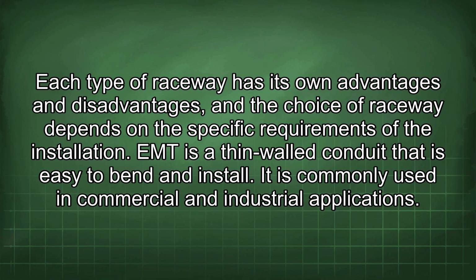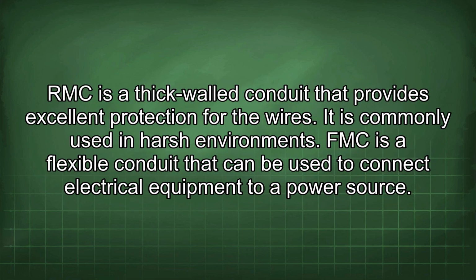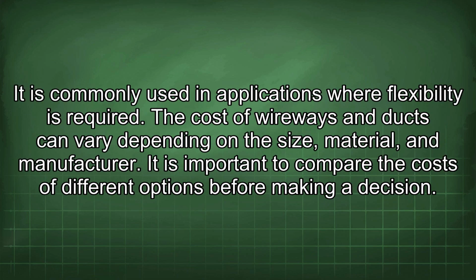EMT is a thin walled conduit that is easy to bend and install. It is commonly used in commercial and industrial applications. RMC is a thick-walled conduit that provides excellent protection for the wires. It is commonly used in harsh environments. FMC is a flexible conduit that can be used to connect electrical equipment to a power source. It is commonly used in applications where flexibility is required.